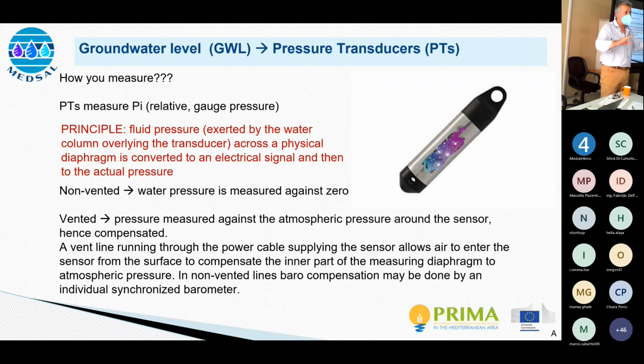All right? Is it as simple as that and we're done? Unfortunately, not. There is another compensation that is required. And this extra compensation has to do with the barometric pressure. Okay? And what does this have to do with the measurement of the pressure? It has to do with the fact that if you're measuring the pressure that is exerted on a gauge because of the water column alone, you need to compensate this pressure for the barometric effects.